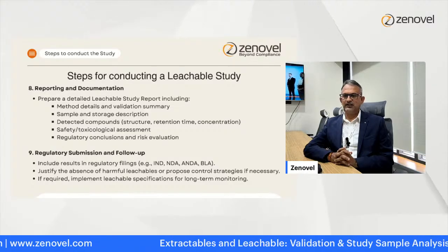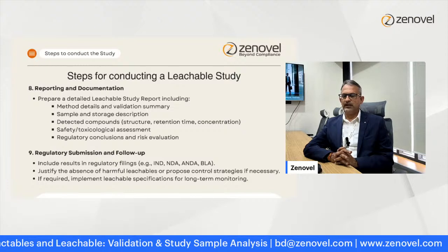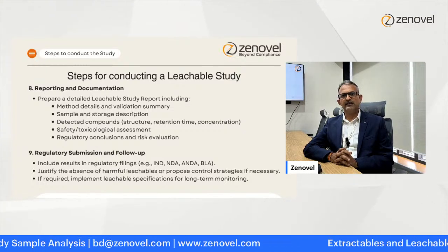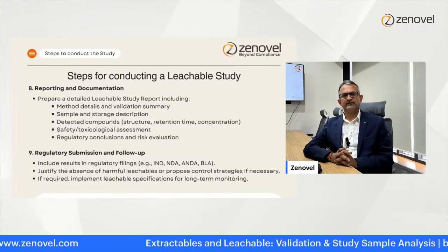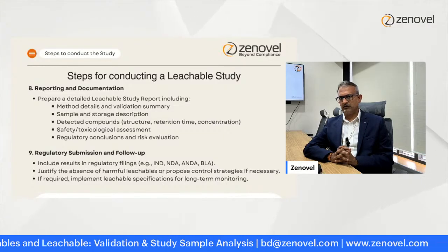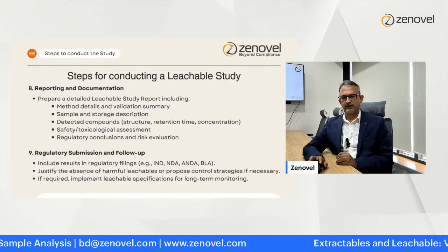From ACT we can derive the AET value, and from the AET we have to calculate our LLOQ value. AET is the analytical evaluation threshold, and ACT is a value that can be useful for the estimation of the AET value.